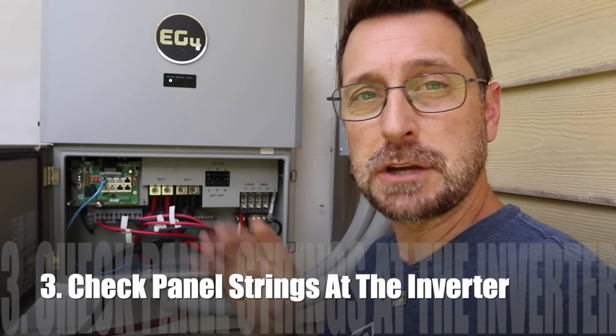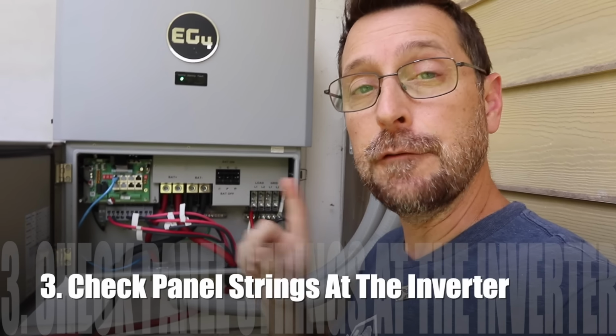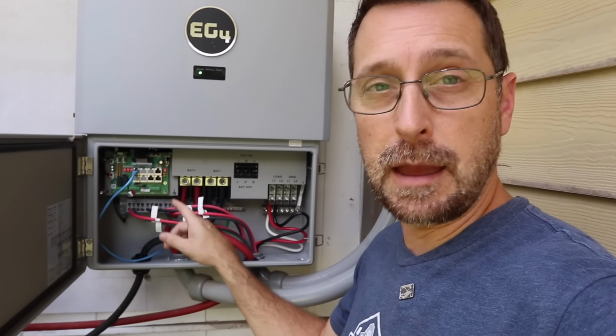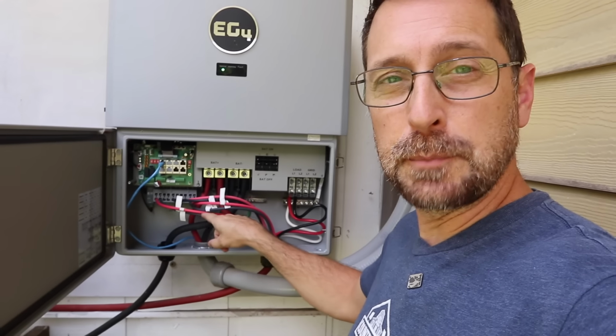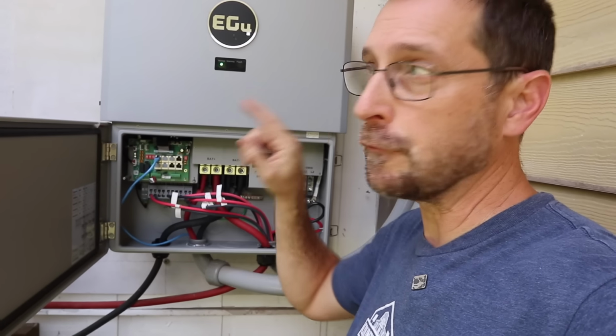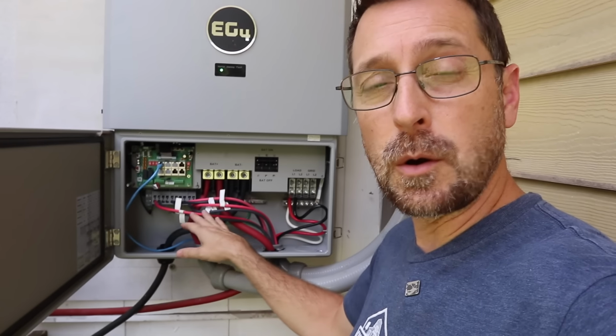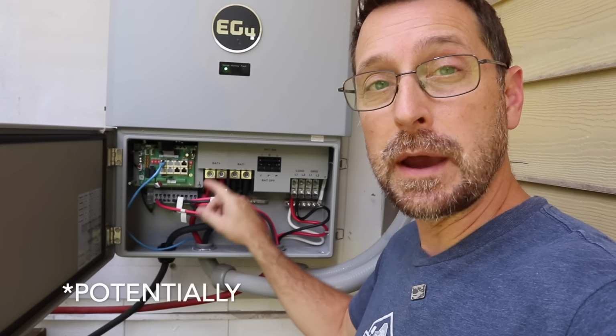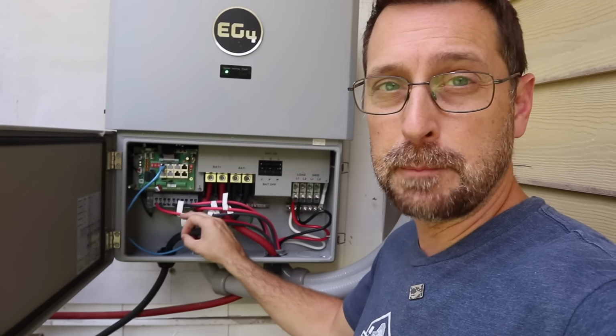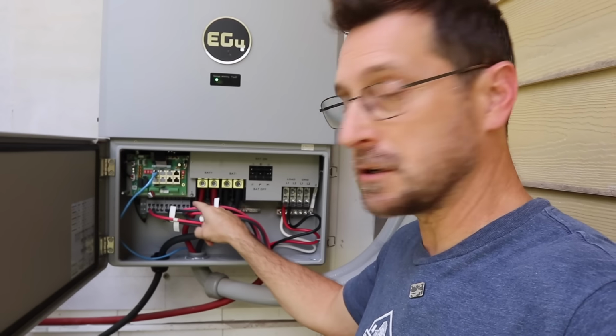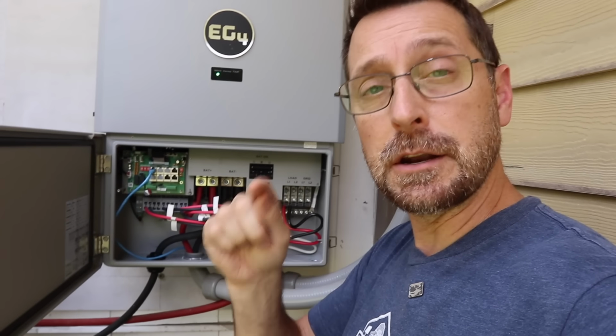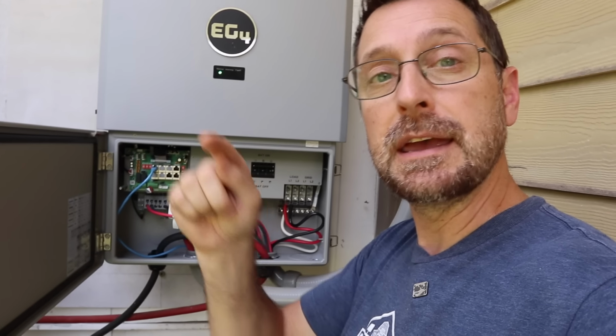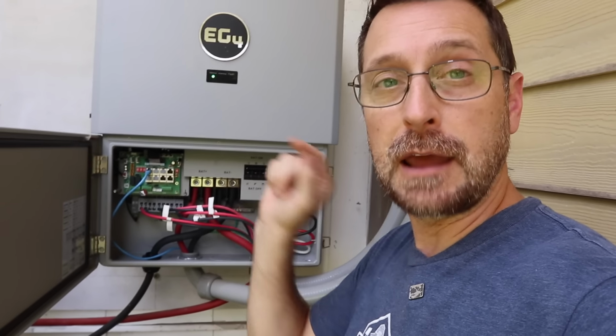Now, you do want to check at your inverter to see if you have trouble with one of your MPPTs. Each one of these inputs right here is a string for our PV array. Now, we know that one of these strings is bad, so the way to check to see if it's the MPPT is to switch the strings. Then go to the monitoring app and see if that bad string has changed to a different MPPT.